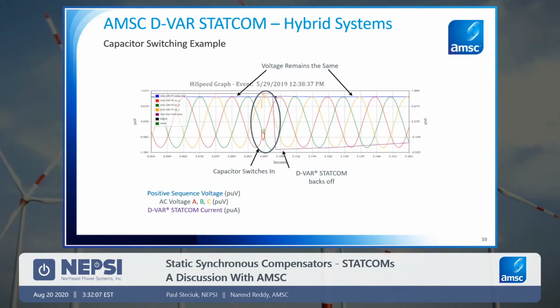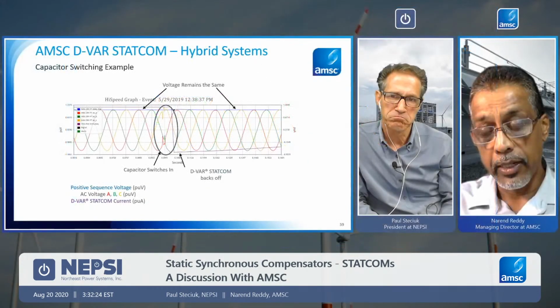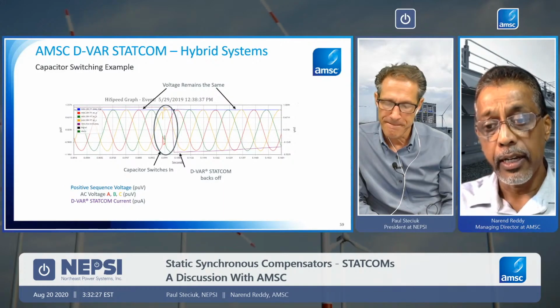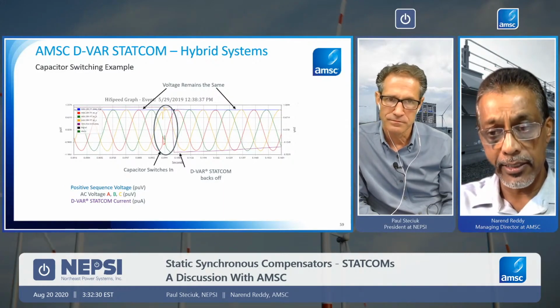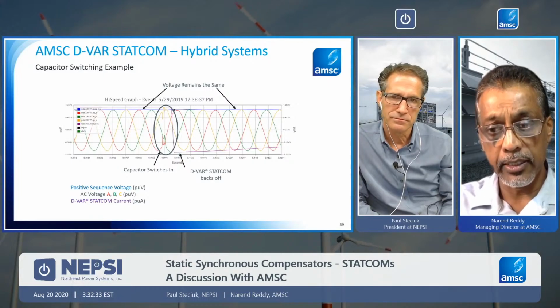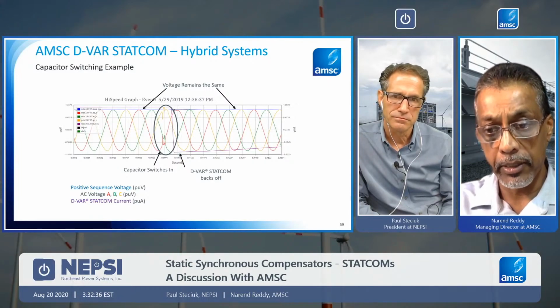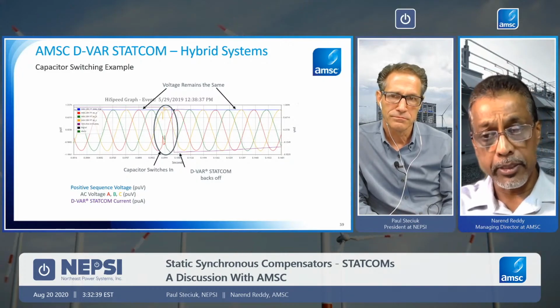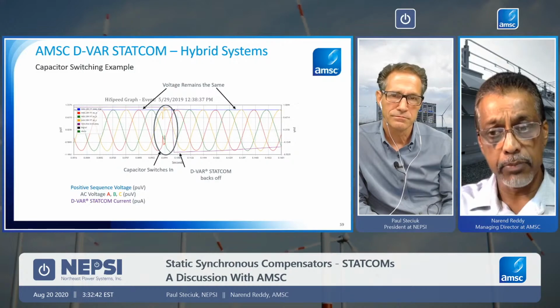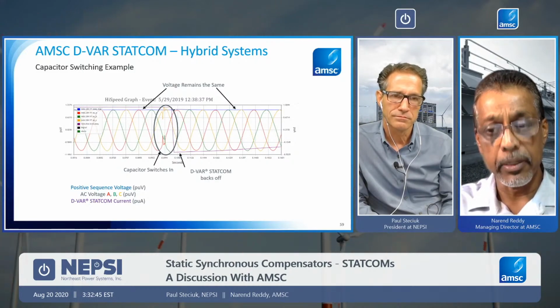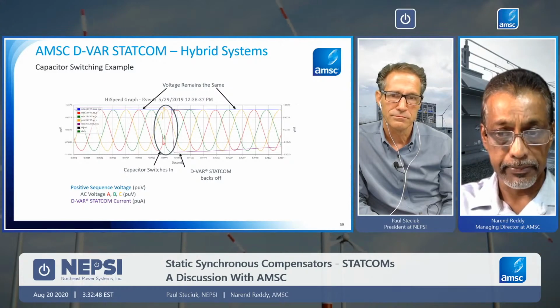But if you look at it a cycle or two later, after all three phases of the cap bank have been switched in, you will see that the voltage magnitude after bringing in the capacitor bank is almost the same as the one before the cap was switched in. Now, how that works is that the DVAR, basically being a dynamic device, regulates its dynamic output in such a way that it offsets the impact of the capacitor bank either coming in or going out. And so this is where a hybrid solution with this functionality really gives you the performance of a fully dynamic system, but in a much more cost-effective way.